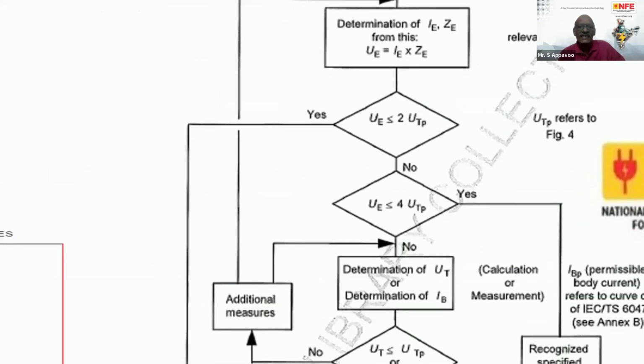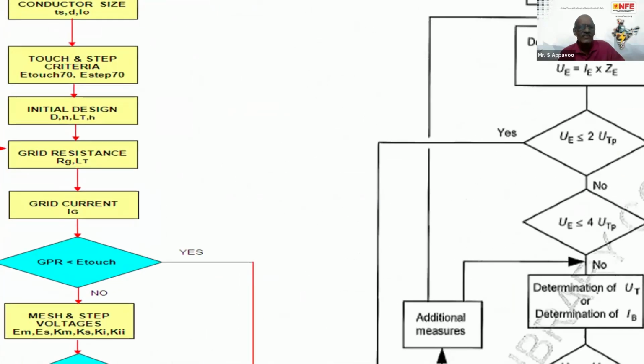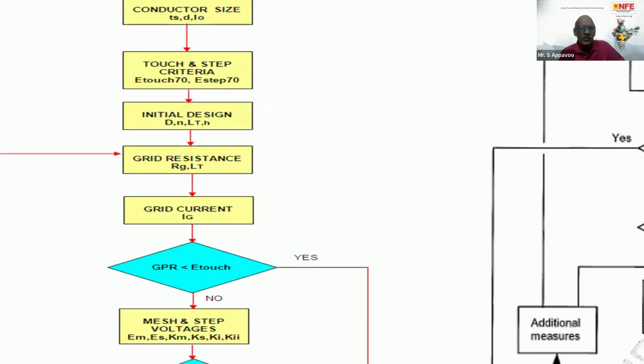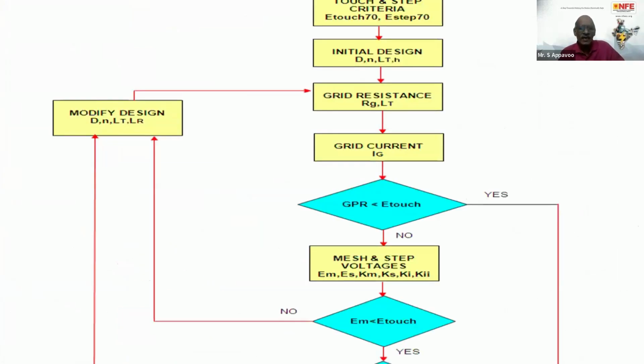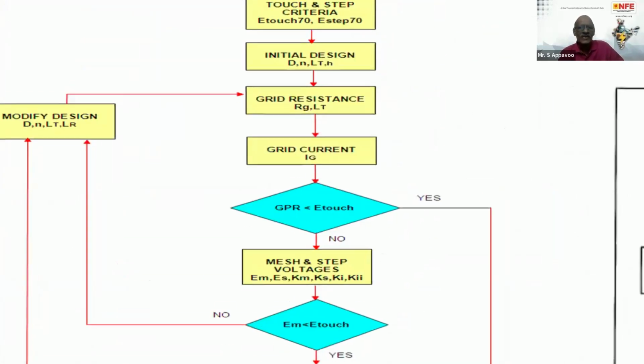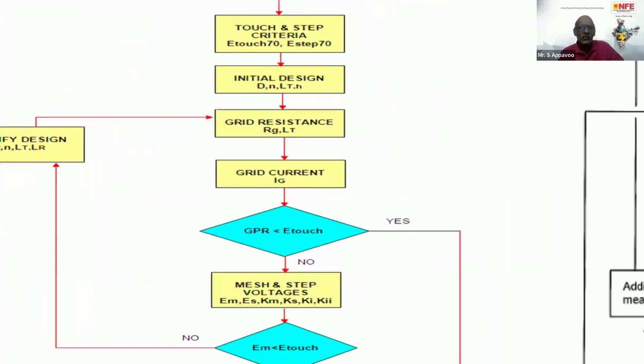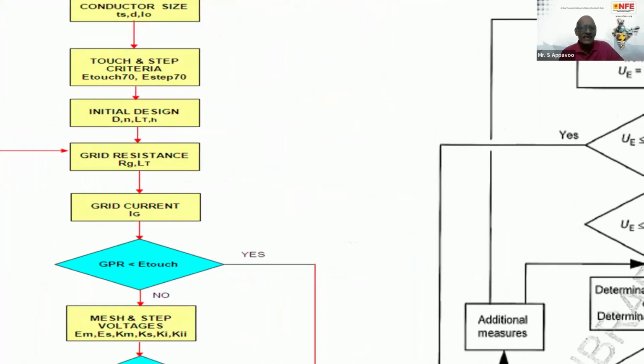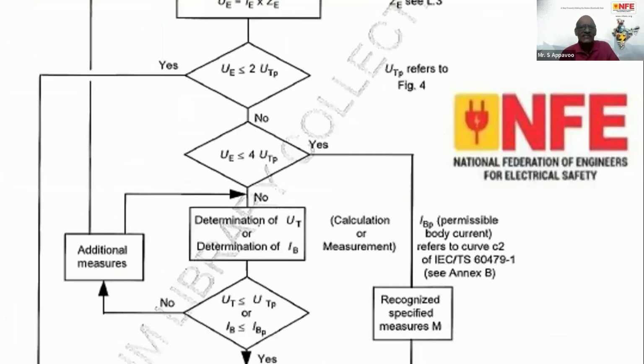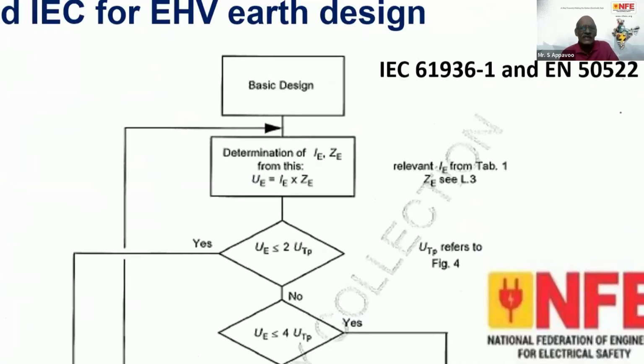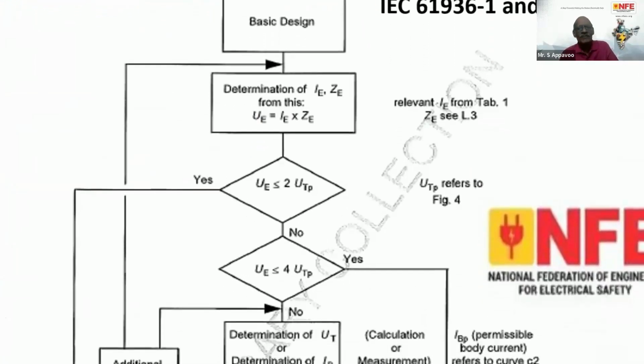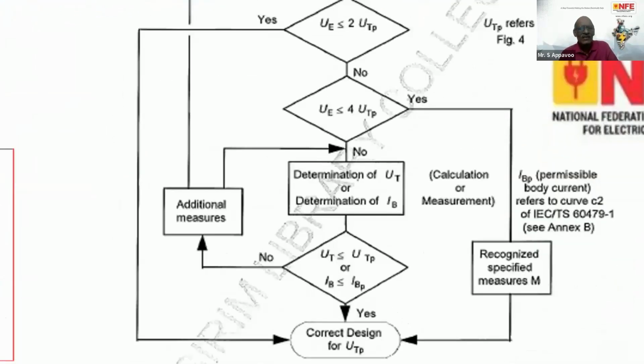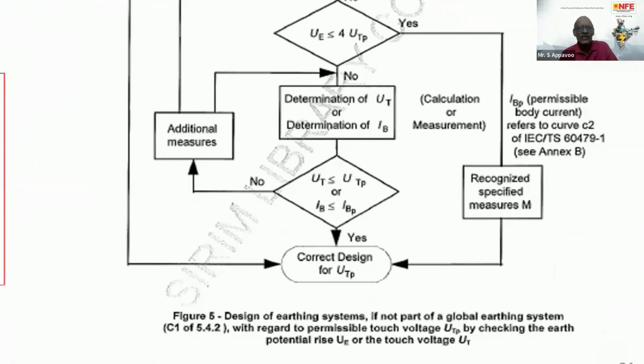See what is available. You can see the flow chart between these two things. There are so many loops, so many feedback systems. Here, you have to go for grid resistance. Then, if it is not sufficient, you have to again attend to the mesh. So here it is very simple. You determine if it is less than the touch potential as per the curve already told, then go for this. It is fine, your design is complete.